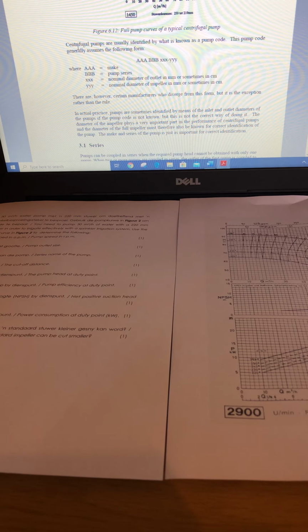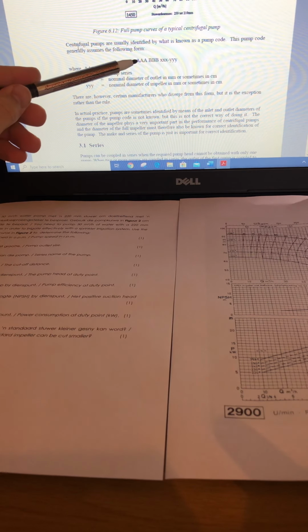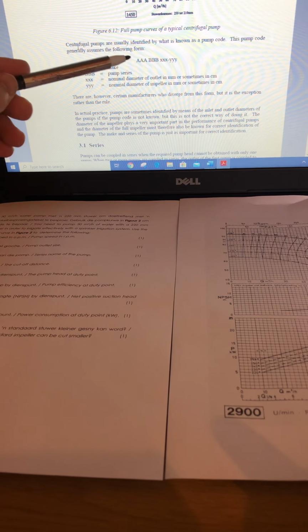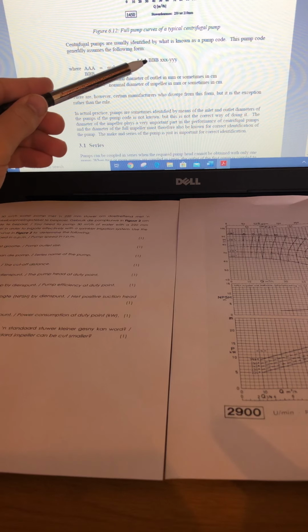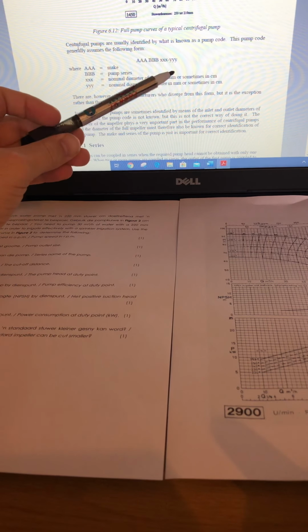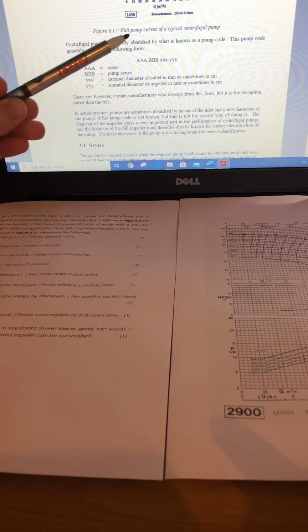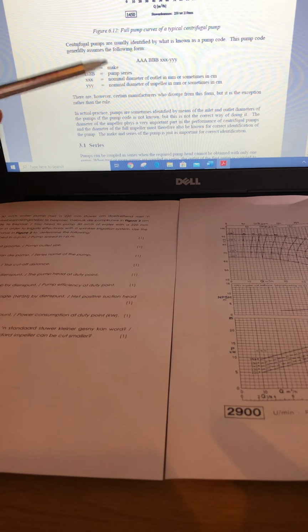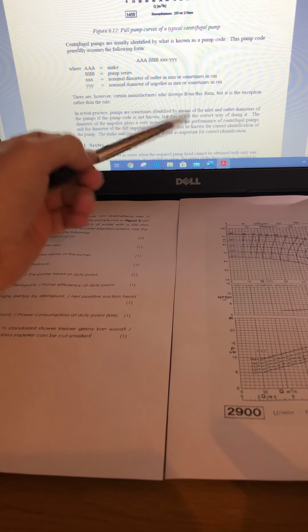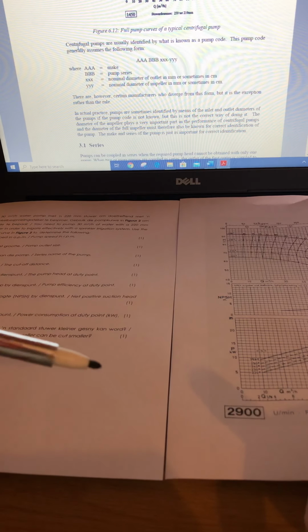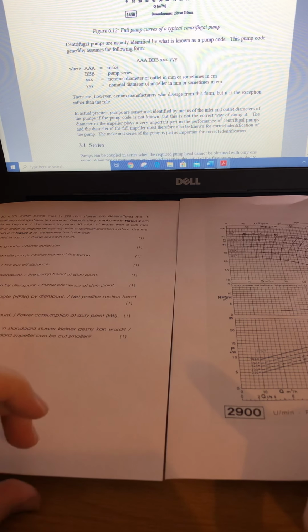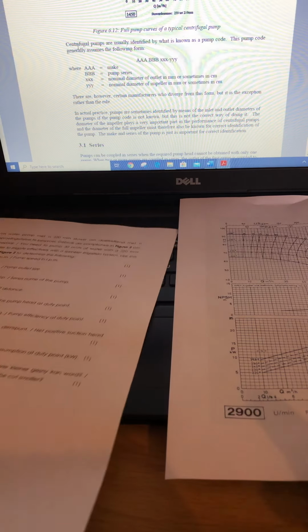It gives you this line that says centrifugal pumps are usually identified by what is known as a pump code. The pump code generally assumes the following form. So you've got your pump code, then you've got that AAA, which is the make, triple B, which is the pump series, the nominal diameter of outlet in millimeters, and then lastly that triple Y is the nominal diameter of the impeller in millimeters or sometimes in centimeters.